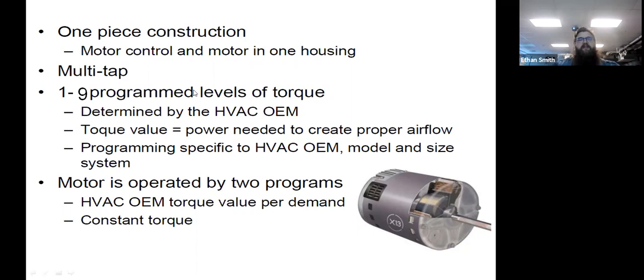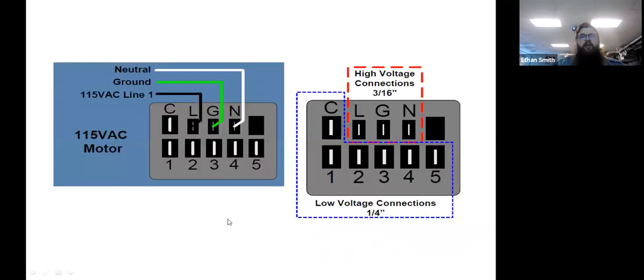Okay. These can be programmed by every OEM manufacturer out there. And they set them to a torque value, which is basically a speed that this thing needs to operate at. So it's going to run at that constant torque value no matter what. We do get a little better performance on high static than we do out of a PSC, but that gain is pretty marginal. So these can be programmed for up to 9 speeds. And when you look at the plugs, this is what you'll see. Across the top of the plug, you'll have a line, a neutral, and a ground, and a 24-volt common terminal. Across the bottom, you'll have speed taps 1 through 5.